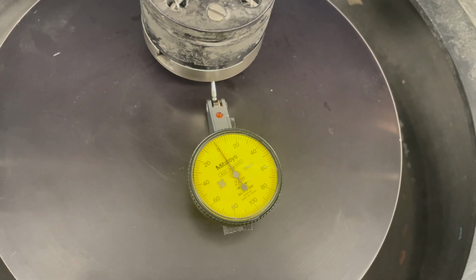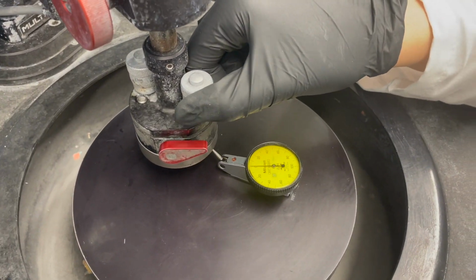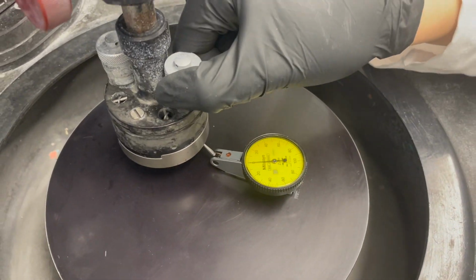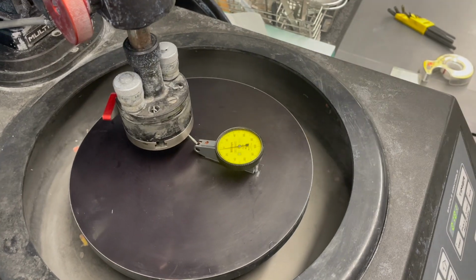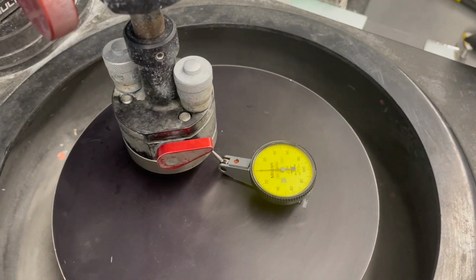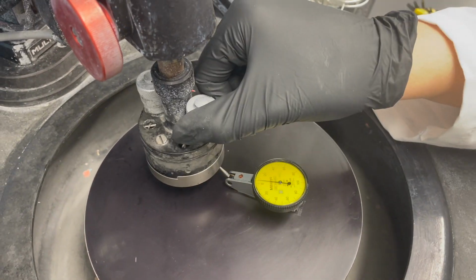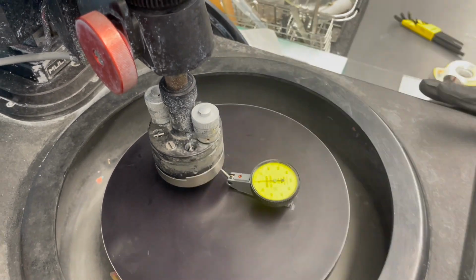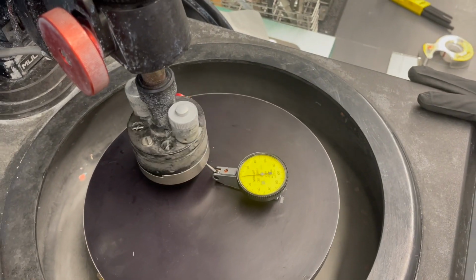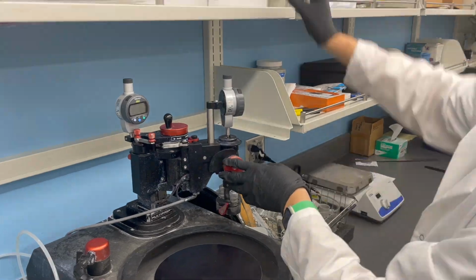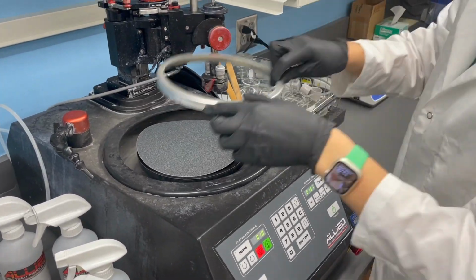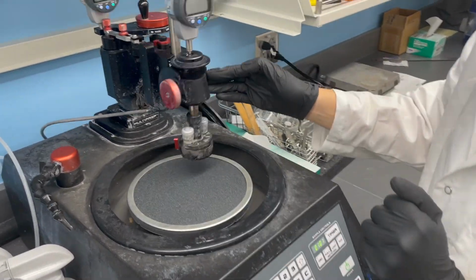Use the full button to rotate the head to the first silver knob. Gently adjust till the dial returns to 0. Repeat at the next silver knob. Rotate to the screw and raise or lower the arm accordingly. Iterate through until the head can rotate 360 degrees and the dial remains at 0. Now you are calibrated. Remove the calibration tools and unscrew the arm so you can place your first grit paper.